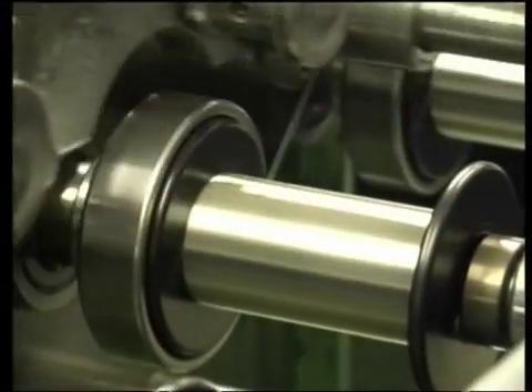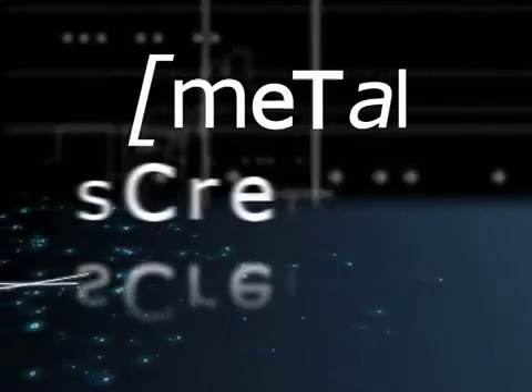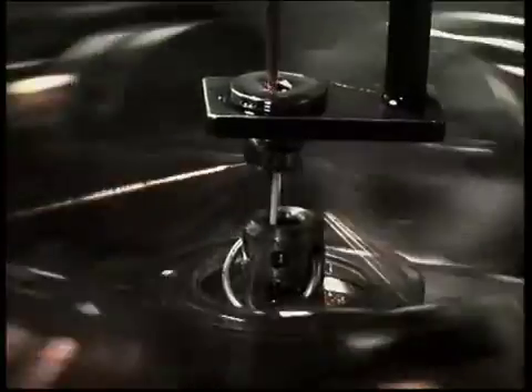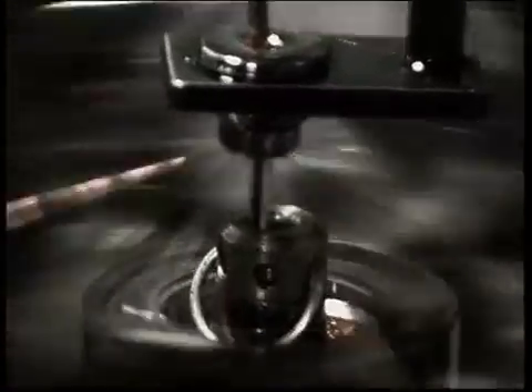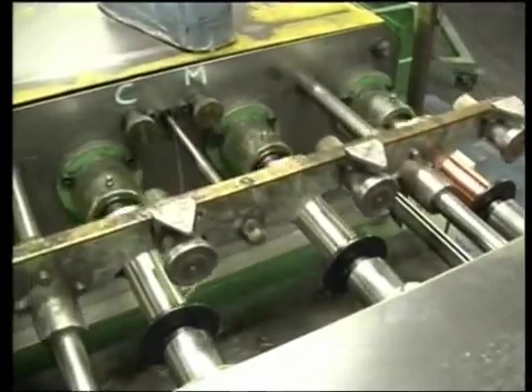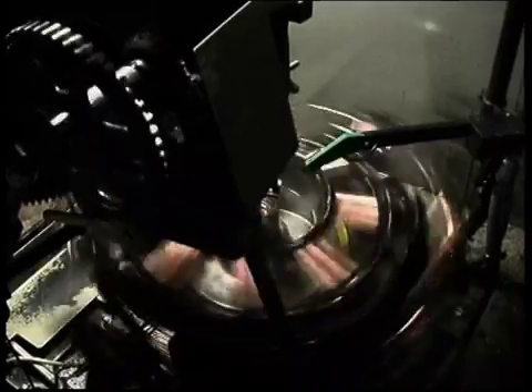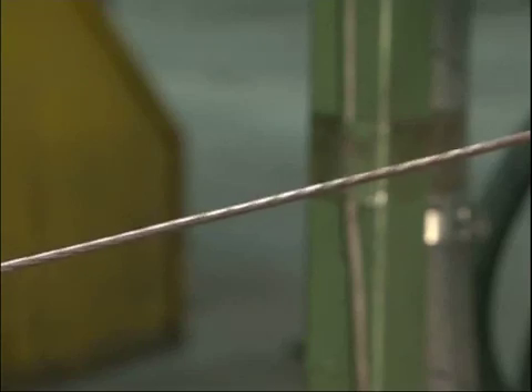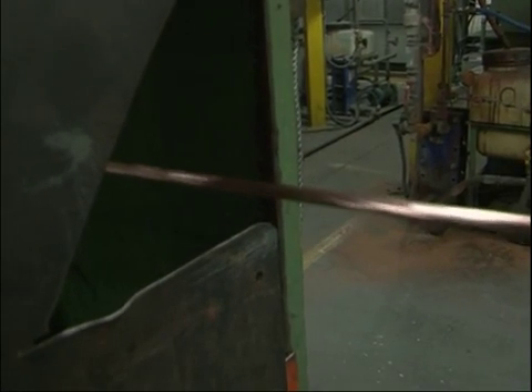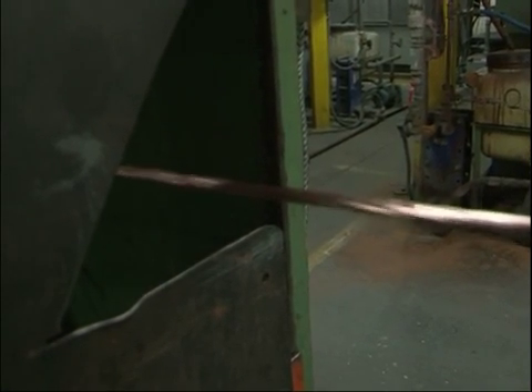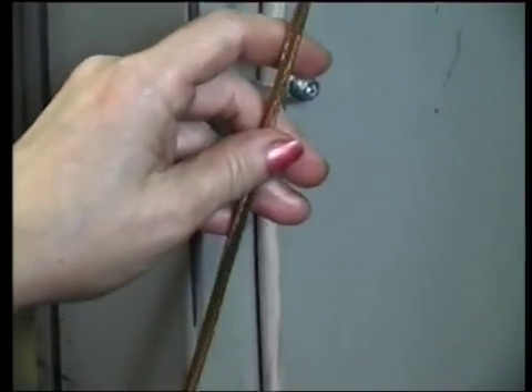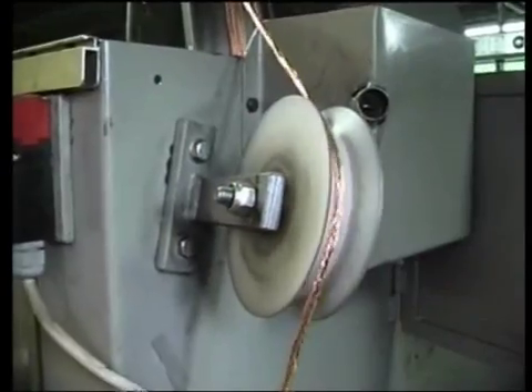All medium voltage cables must have metal screens, which may be individual on each core or collective where the cores meet. The standard provides the manufacturing characteristics of the various types of armour allowed and the physical and chemical characteristics for the various materials affected. The advantages of metal armour include the ability to resist better in the case of high pulling forces.